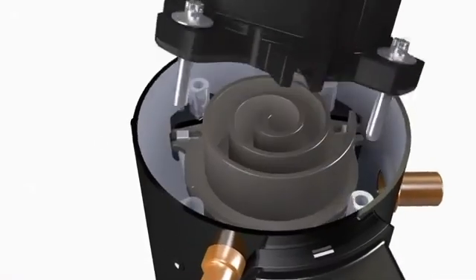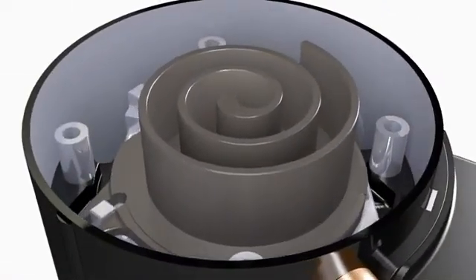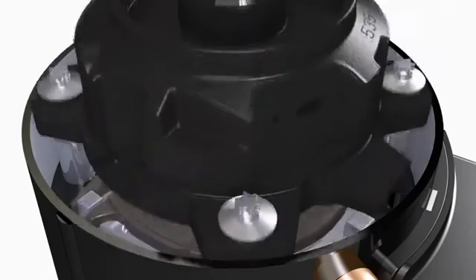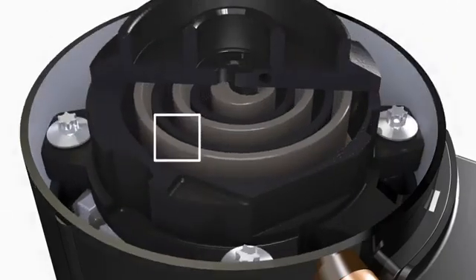The Copeland Scroll Compressor design is comprised of mechanically compliant cast-iron sealing surfaces. Inherent forces cause the scrolls to continuously seal against each other, even as wear occurs. This wear-in versus wear-out design ensures high efficiencies and avoids the pitfalls of other tip-sealed designs, which often wear out prematurely, causing performance degradation and shorter compressor life.